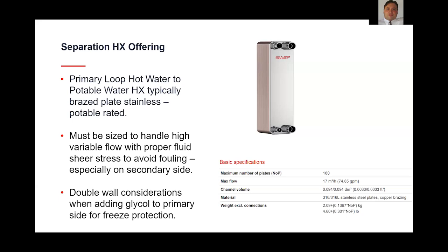You have to look at multiple sizing criteria. It's important to make sure that you have a specific fluid film shear stress in between the plates for the majority of the operating hours to avoid corrosion because of that potable side and mineral deposits that could occur if you don't maintain sufficient velocities through this. So usually manufacturers are selecting these specifically and pairing them and offering them as part of the package. So it's important to comply with that and typically not source them from third parties.